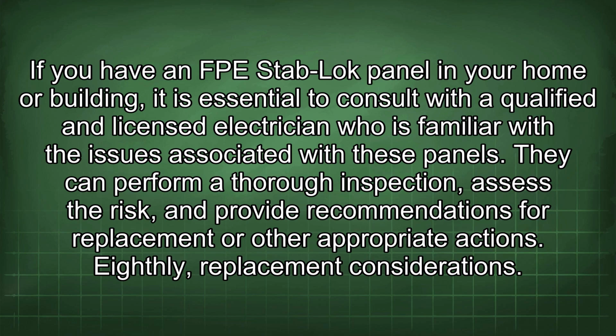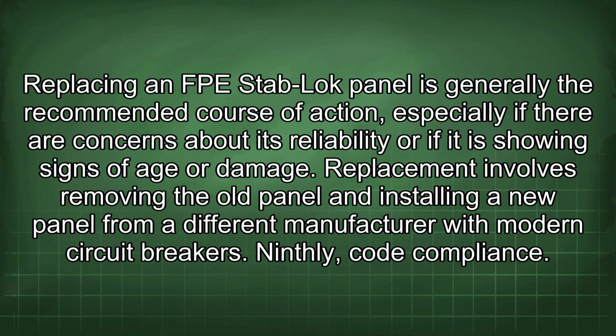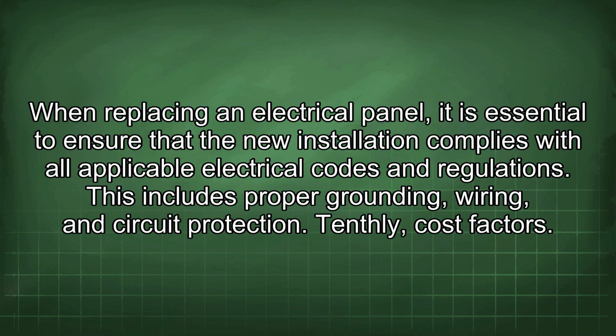Eighthly, replacement considerations. Replacing an FPE Stab-Lok panel is generally the recommended course of action, especially if there are concerns about its reliability or if it is showing signs of age or damage. Replacement involves removing the old panel and installing a new panel from a different manufacturer with modern circuit breakers. Ninthly, code compliance. When replacing an electrical panel, it is essential to ensure that the new installation complies with all applicable electrical codes and regulations. This includes proper grounding, wiring, and circuit protection.